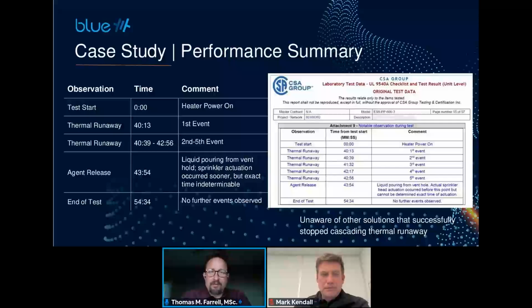And at 43:54, you can visibly see a little bit of excess agent pouring through the vent holes in the top of that battery. But once it was submerged, there were no more thermal events. So the whole thing was over in about 3.5 minutes. And that's really good performance when you're talking about an entire rack of lithium ion batteries with one module experiencing thermal runaway.